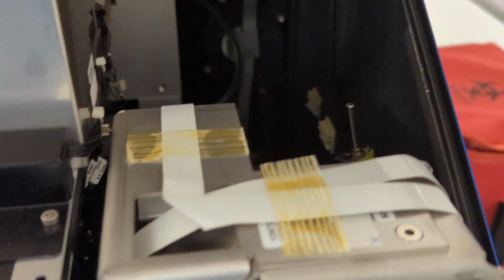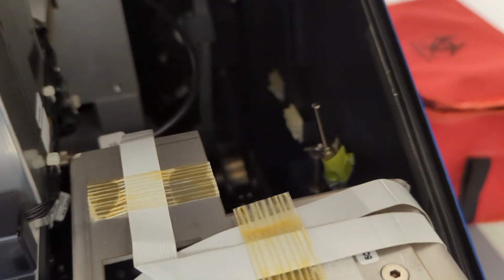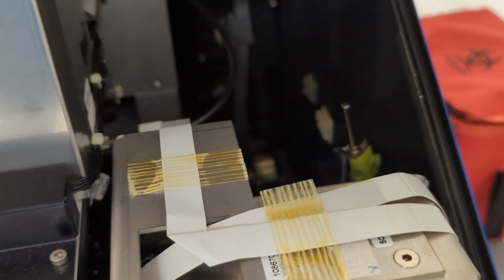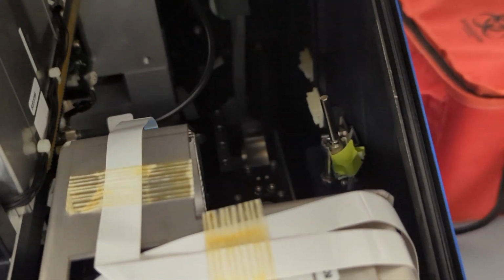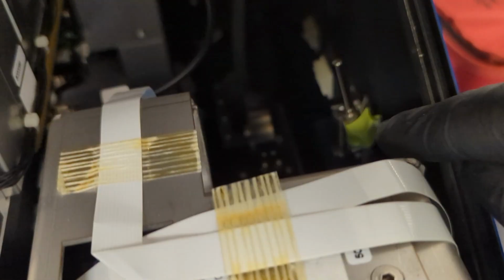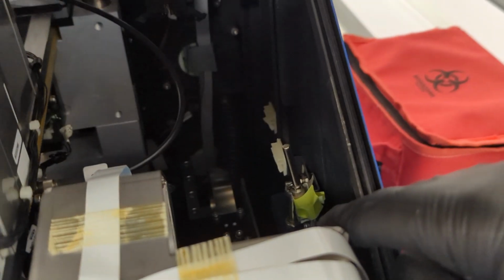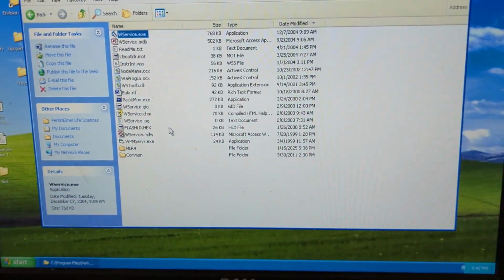One thing that you can do to run the instrument, if you want to check a few things like run a dummy plate, is keep the lid open and trick it, because it's just using a Hall sensor to sense whether or not this lid is closed. And so I've just got a magnet there tricking it. But you don't need that for the service mode application, which is what I'm going to show you right now.